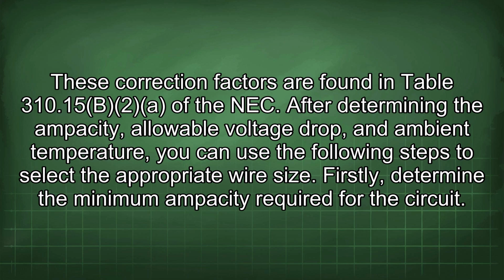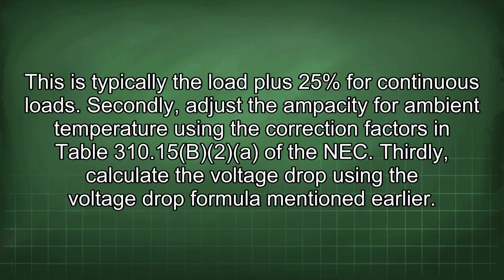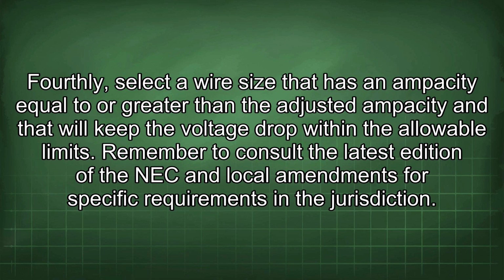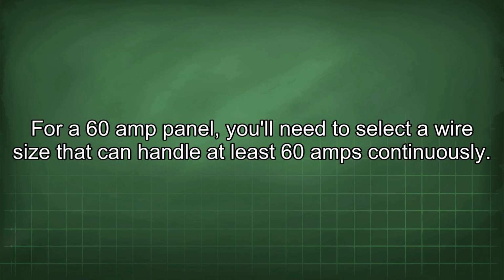Firstly, determine the minimum ampacity required for the circuit. This is typically the load plus 25% for continuous loads. Secondly, adjust the ampacity for ambient temperature using the correction factors in Table 310.15(B)(2) of the NEC. Thirdly, calculate the voltage drop using the voltage drop formula mentioned earlier. Fourthly, select a wire size that has an ampacity equal to or greater than the adjusted ampacity and that will keep the voltage drop within the allowable limits. Remember to consult the latest edition of the NEC and local amendments for specific requirements in the jurisdiction. For a 60 amp panel, you'll need to select a wire size that can handle at least 60 amps continuously.